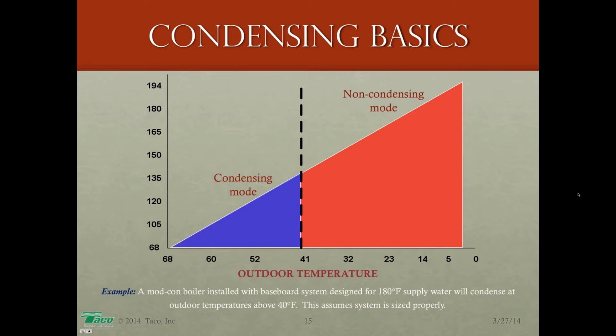Some condensing basics. And this is something I've heard so often over the years. If you have a fin tube baseboard system and you have to run 180-degree water, it's just silly to put in a ModCon boiler. It's a waste. It'll never condense. It's going to run up to 180 degrees. It's not going to be efficient. It's a waste of money. You're better off with a cast iron boiler.